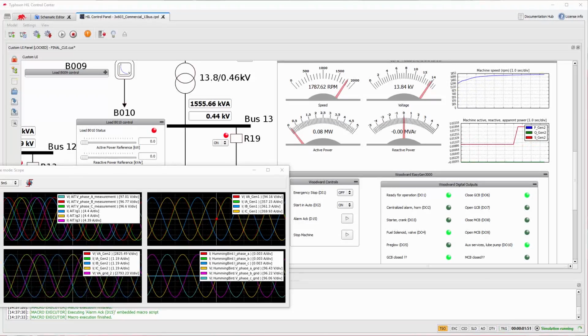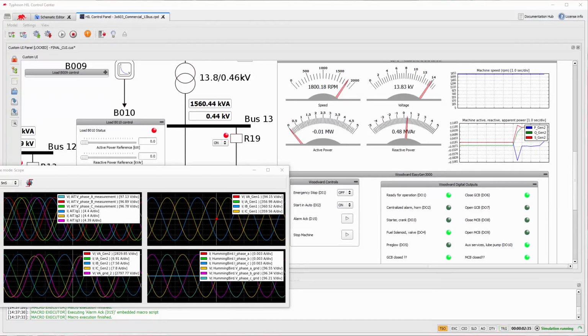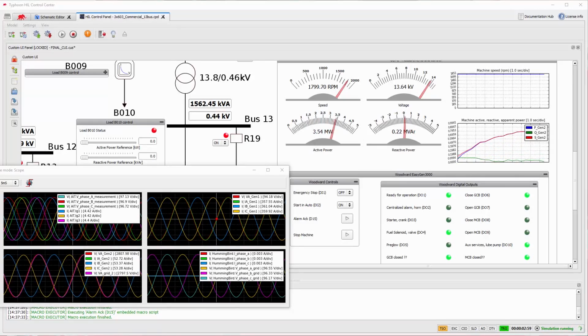To observe this process, let us take a look into our scope. In the third viewport, we can see the waveforms respective to the Gen 2. The magenta sine wave is the phase A voltage at the Genset point of connection. The red and green sine waves are the voltage and current respectively at the Genset terminal. Once the current and voltage are in phase with the point of connection voltage, the Woodward sends the command to close the contactors and connect to the grid. Once connected, it will ramp up the power to the set point defined.